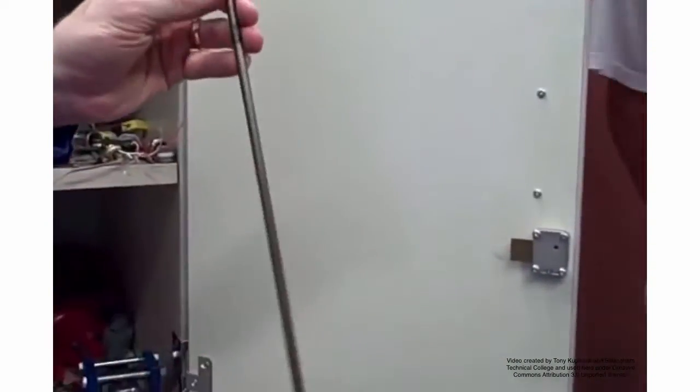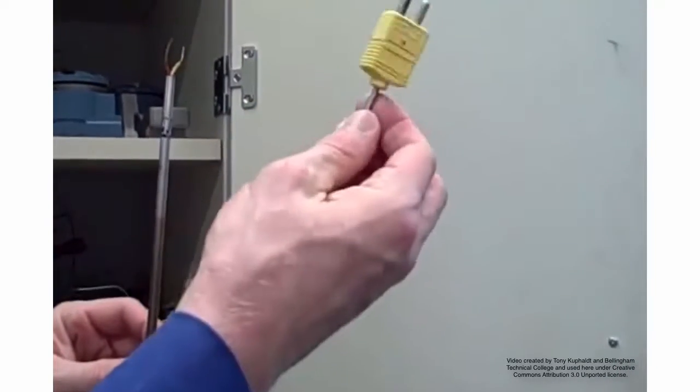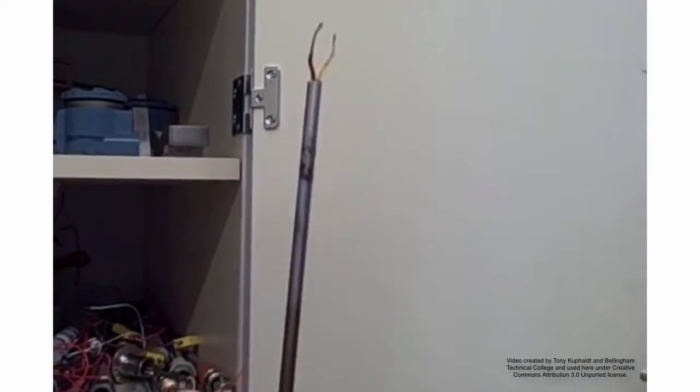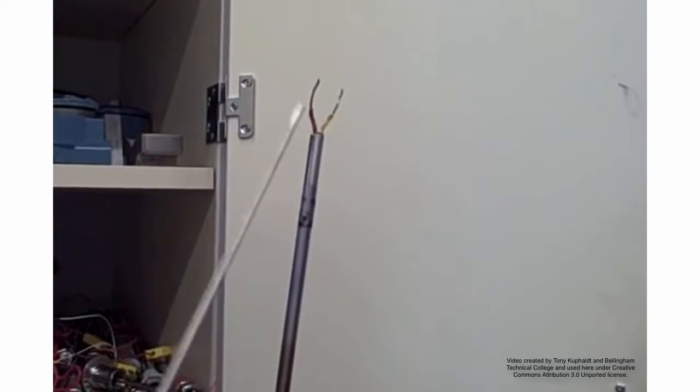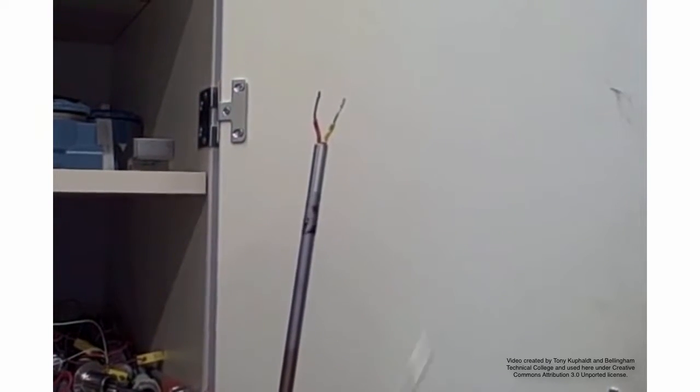We also have another version of an industrial thermocouple. This one right here does not have a molded plug. It just has two wires coming up. We can tell from that it is also a type K, yellow and red, red being negative, yellow being positive.